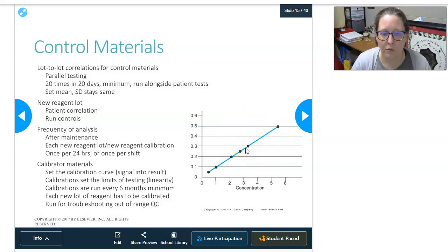Calibrations are run every 6 months at the bare minimum. Again, a lot of that is going to be manufacturer determined. You will always run calibrations for each new lot of reagents. Always, like you can't even run the test until you've calibrated it. And you can also use calibrations to troubleshoot out of range QC. Sometimes the test just needs to be recalibrated, and that fixes your problems. So it's one of the tools that you can use to figure out what's going on with your analyzer.